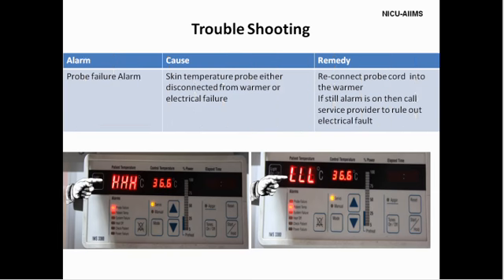The probe failure alarm may be active in the servo mode of operation, and it activates when the skin temperature probe fails electrically, either due to an open or a short circuit, or is disconnected from the warmer. The heater deactivates and the patient temperature display flashes either HHH or LLL when this alarm condition exists. Reconnect the probe into the socket, and if the alarm still remains activated, we may have to call the service provider.